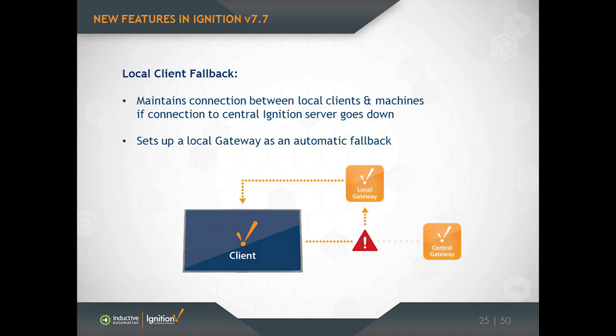But if the connection to that central gateway is interrupted, that client ceases all functionality. You might want that client to fall back to a basic HMI-type functionality so that even if you can't connect to the central gateway, you maintain your basic control and status functionality on that client. That's what the local client fallback ability gives you.